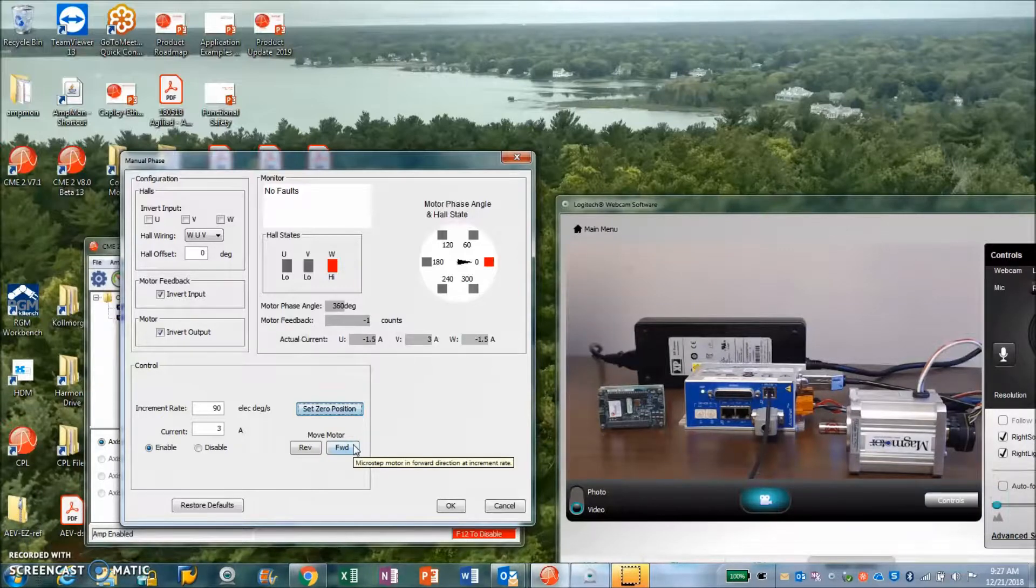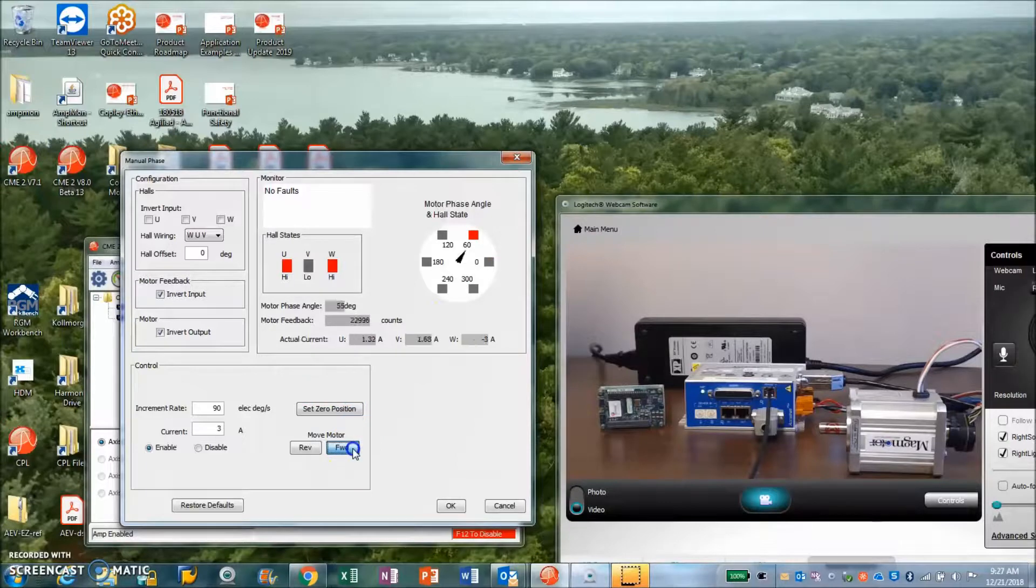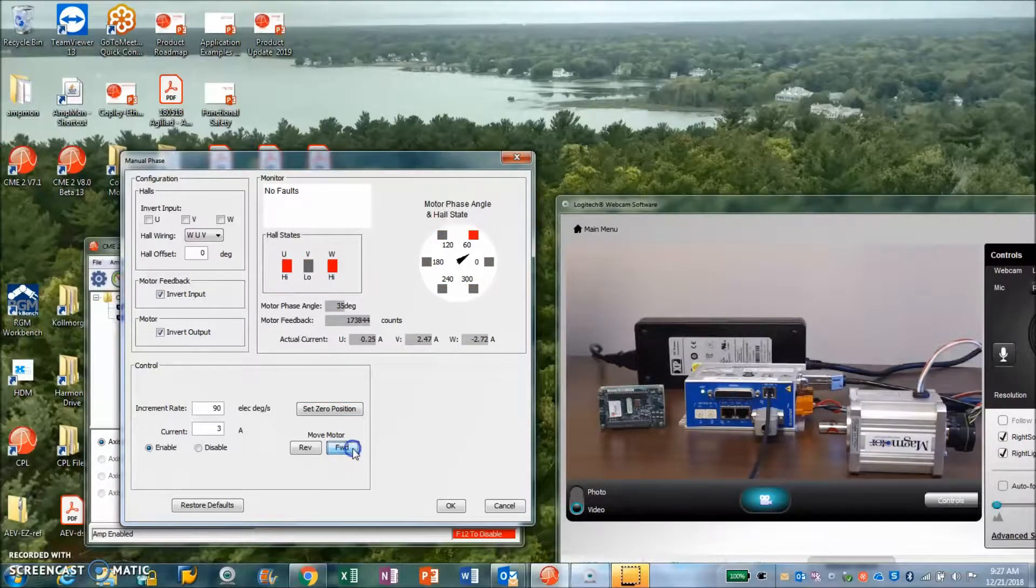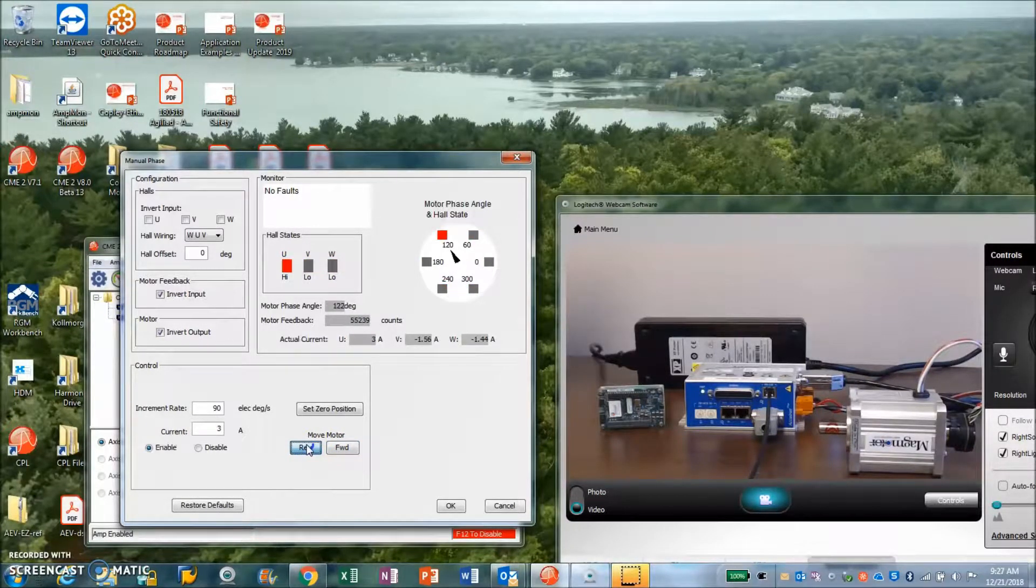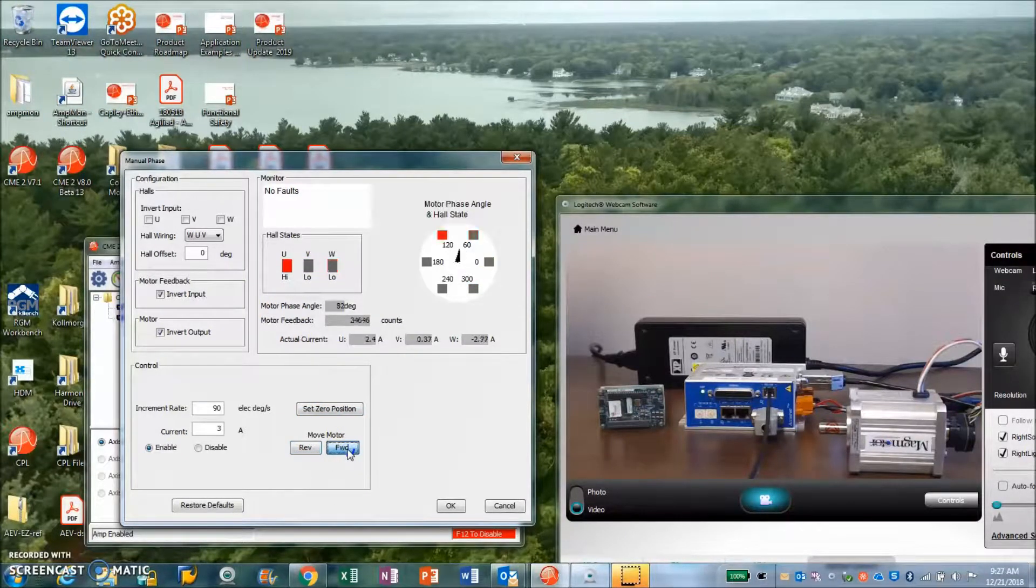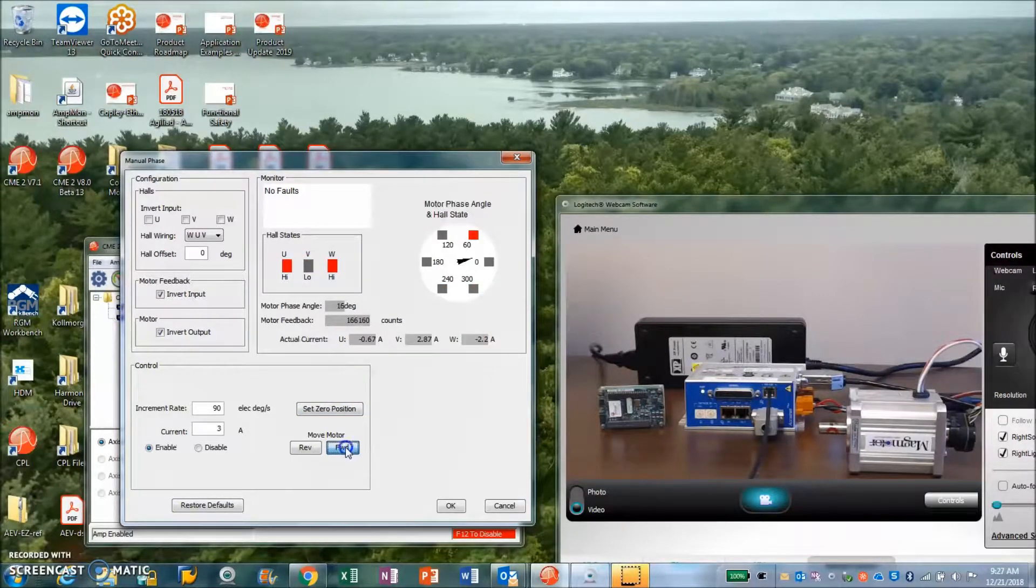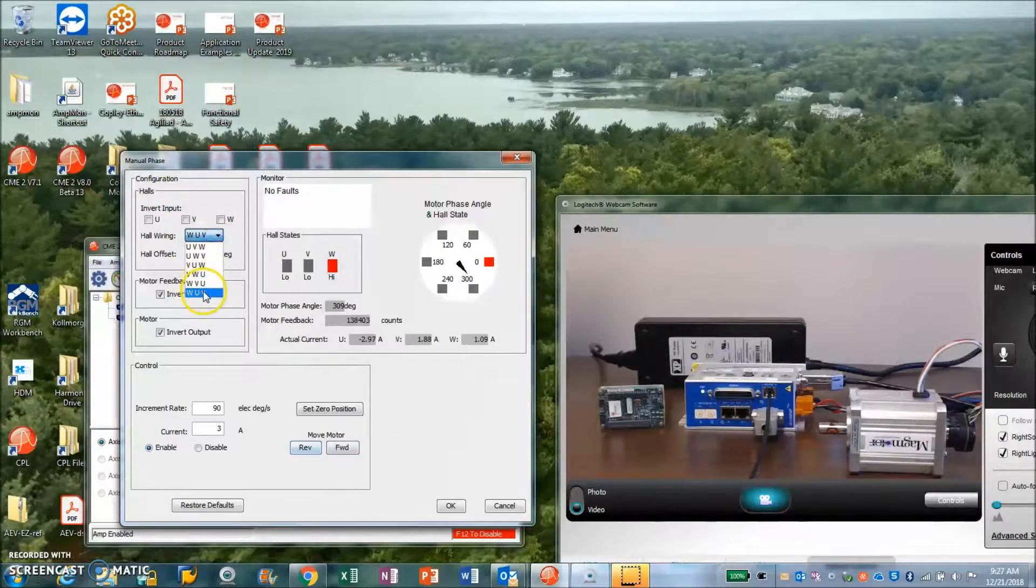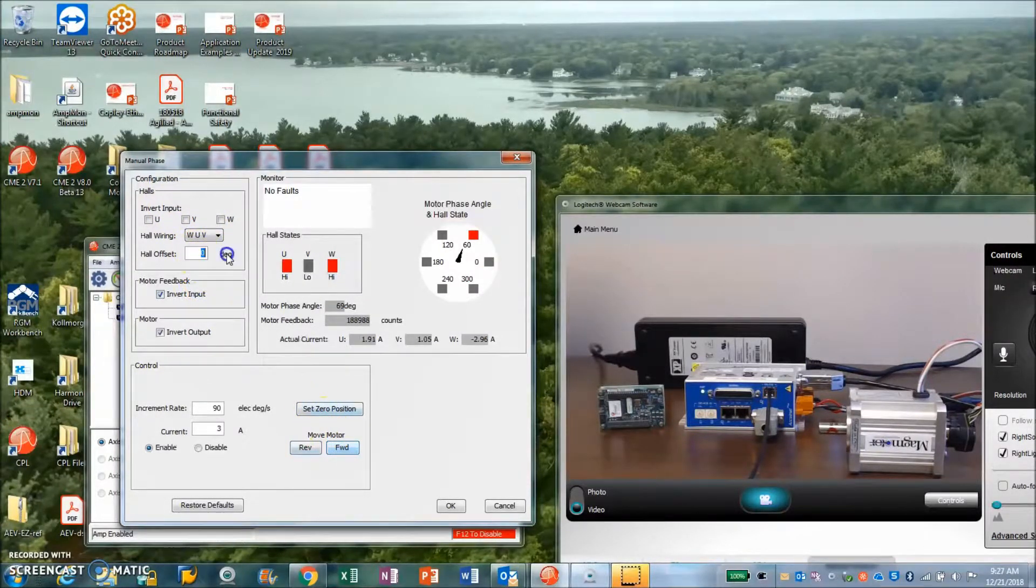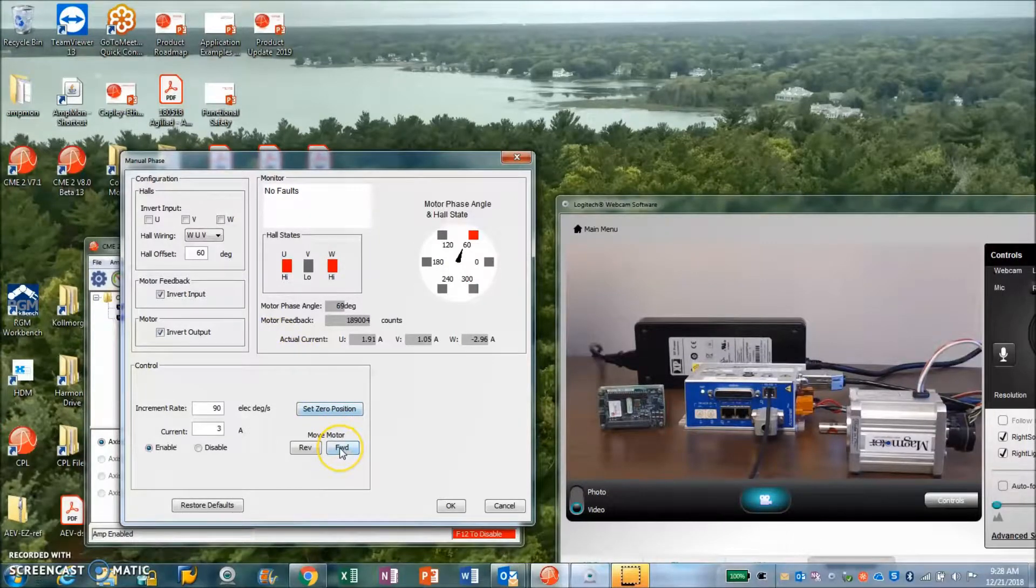After I do the installation in the proper position, I have to figure out the phasing. We'll rotate the current vector and look at the hall indicators to make sure that they're aligned properly. When you go forward, of course counts are going up, and the red indicator should lead in both directions with no load. We can change the hall wiring and the hall offset to get the right alignment.